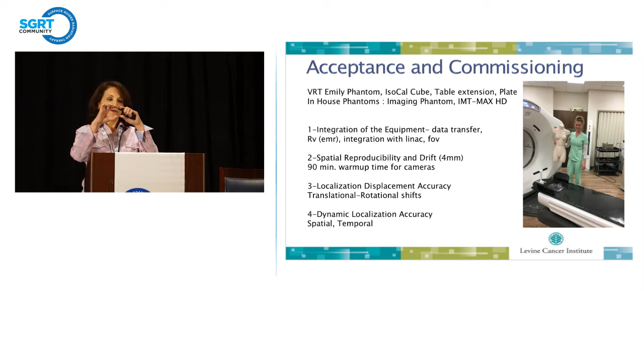And as a precaution now, we don't shut down our cameras. We don't want them to cool down in the morning. We usually have a mark on it that says don't turn off. And if we have to reboot or repower the system, we turn it off. We don't let it cool down, so we don't get this 4 millimeter drift that they cause when they cool down. Or you're not supposed to do QA during that time too.